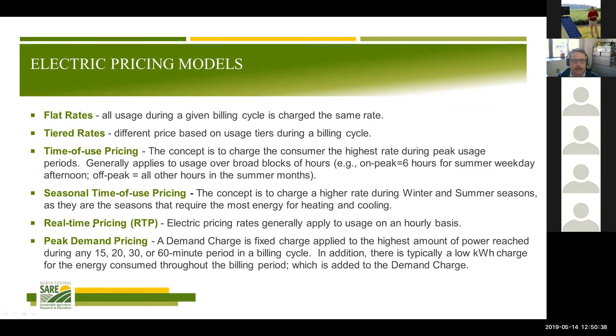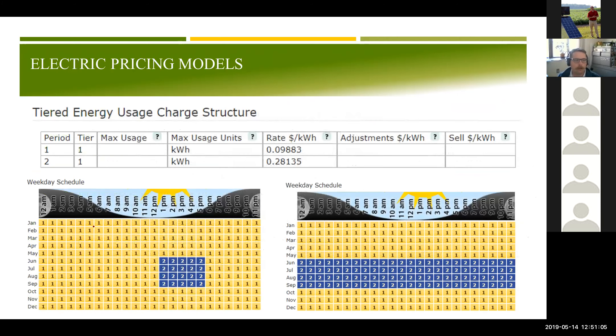Peak demand pricing looks at your peak use at some increment of time and gives you a charge based on that. One challenge with solar is that while it has some impact on demand, it's difficult to model that accurately and guarantee it, so it's very difficult to assume a reduction in demand. Tiered structures are also common — most common in my area is a two-tier structure where winter is one period and summer is another, and sometimes your first few kilowatt-hours are worth one amount and the next kilowatt-hours are worth less.